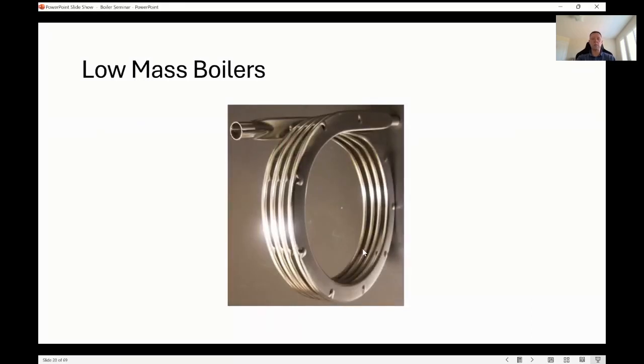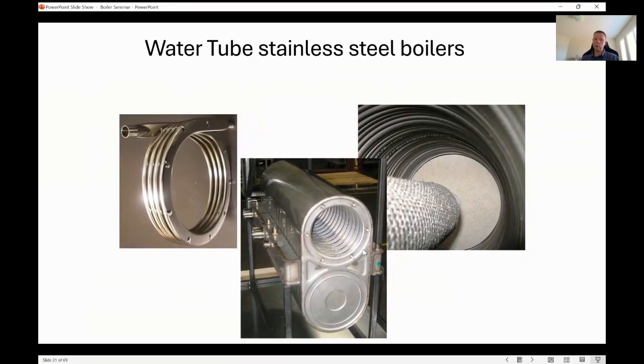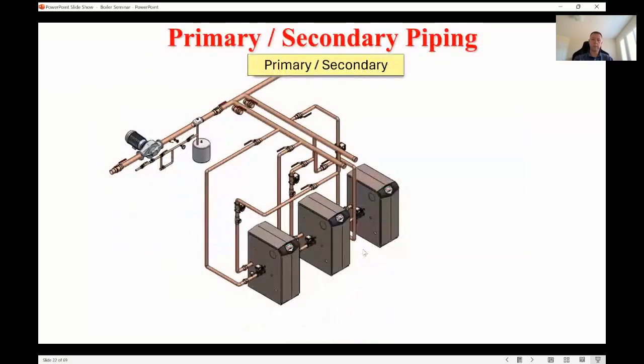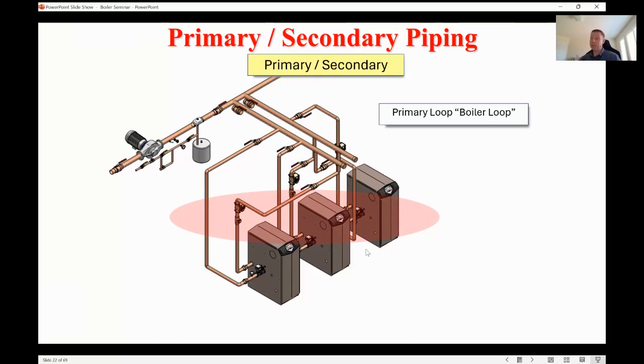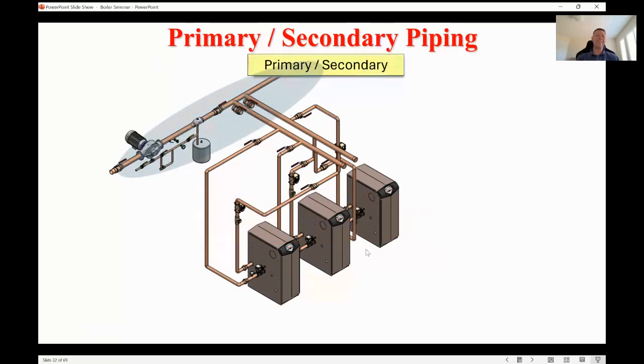So let's focus in a little bit more on low mass boilers to start. As I said, low mass boilers tend to be water tube type boilers where the flue products, the water's in the tubes. The burner is usually in the middle, like I'm showing here, and it's surrounded by the flue products there. Not a lot of water in there, so they heat up really, really quickly. And of course, I said I always recommend primary, secondary piping with these. I think this piping schematic has been around for a long time. I'm sure everybody's familiar with it, but let's do a review. Reviews are always good. The boiler loop is generally always referred to as the primary loop. Can be regional though. The system loop's usually referred to as a secondary loop, right?